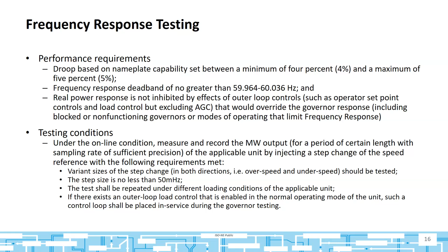And in the next two slides, if we go between them, this is a case where in the commissioning testing that I just described, we were able to see a sluggish response that we were able to work out of the generator by going back to them. In this case, they had enabled some additional capability that was slowing down the response of the frequency responder in response to the change in the reference. And then we worked with them, identified what had been enabled in there.